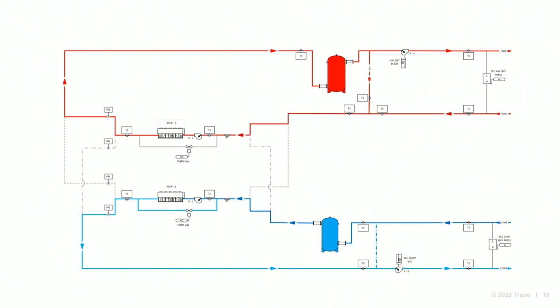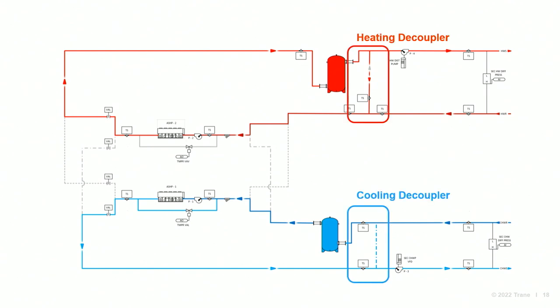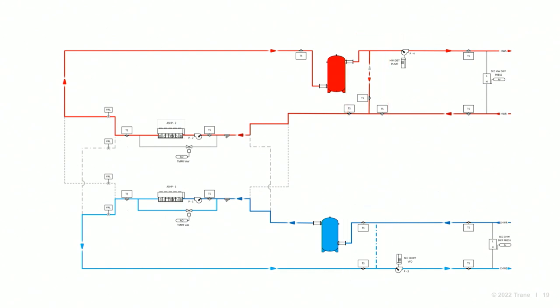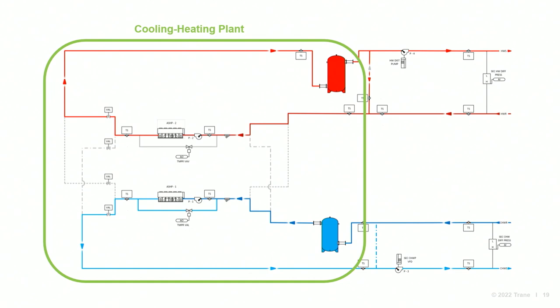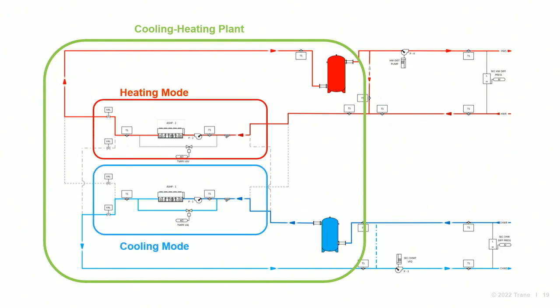Both distribution loops are shown as decoupled from the production loop. This allows for greater flexibility during design as well as eventual operation. Notably, these decoupled systems support any distribution flow or delta T, no matter the flow range of the heat pumps. Additionally, variable size and types of production units can be applied to best meet the building load requirements. Moving into the production loops, we see the air-to-water heat pumps. These units are piped in a dual feed and return piping arrangement. This allows each unit to provide either heating or cooling, irrespective of any other unit's mode of operation. We also show variable production pumping to simplify and positively meet the unit's flow requirements as efficiently as possible.